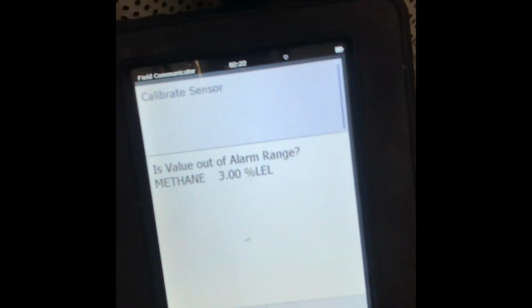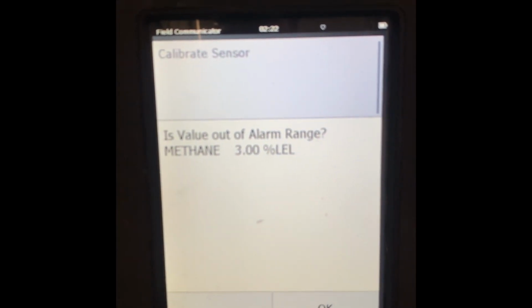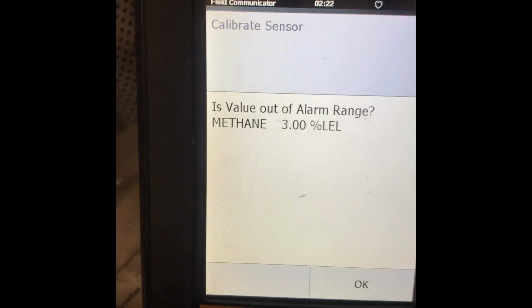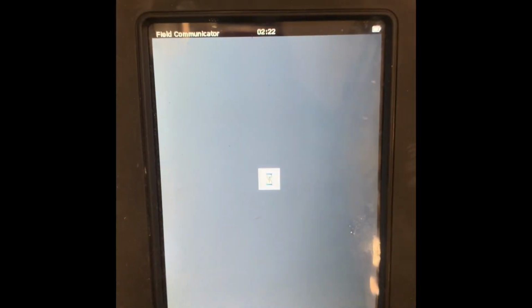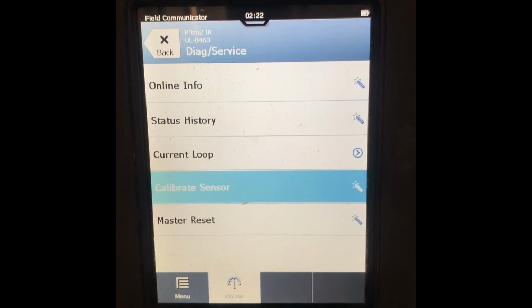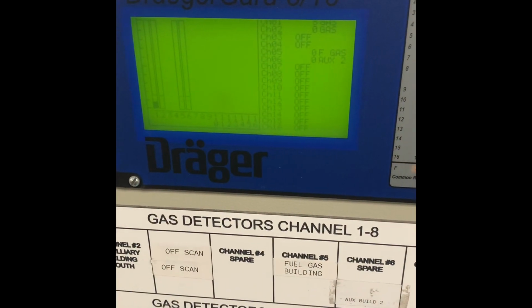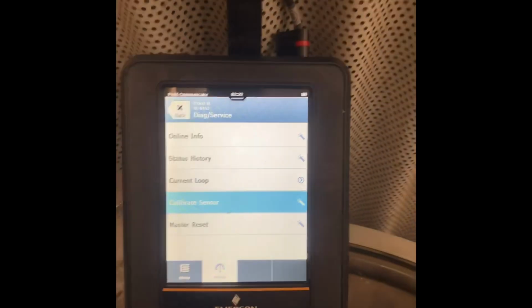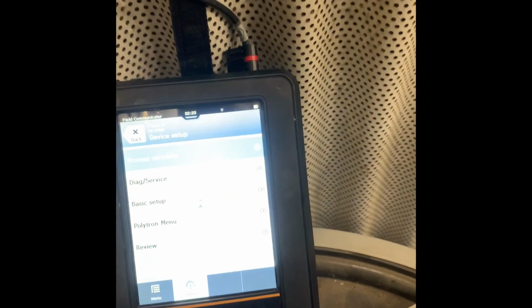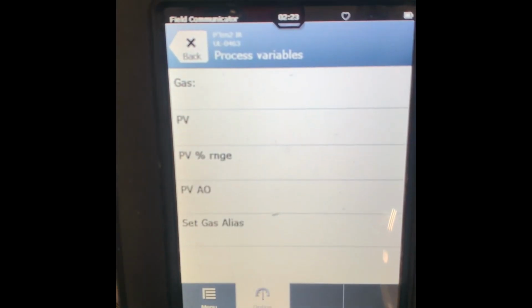So I'm going to push all that methane into it when it's out of test mode, and you'll see that number go way back up, because now all the methane in the tube is getting pushed through the sensor. And I'm going to walk over to the Draeger panel, and yep, it was in alarm when I got here, so it made it back to the panel. The alarm worked.